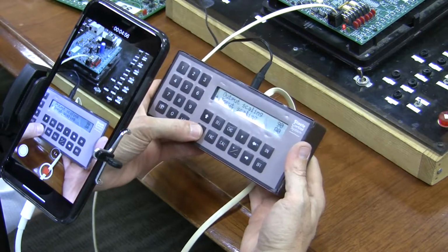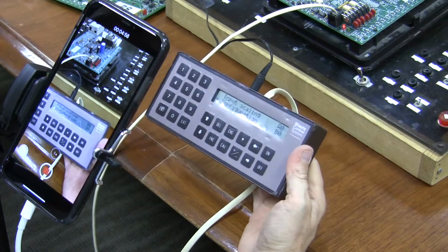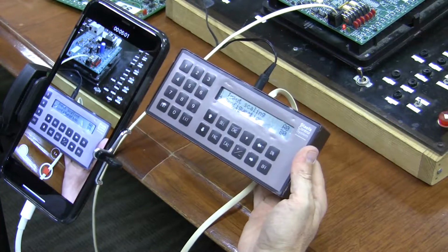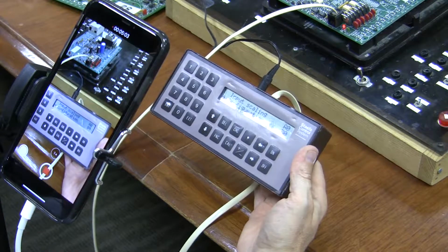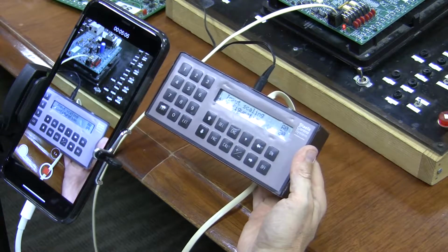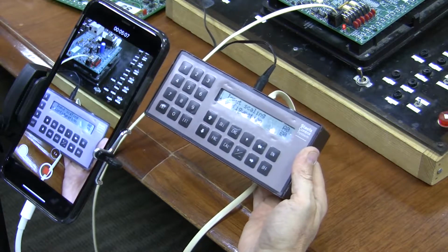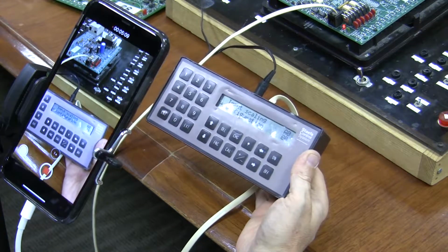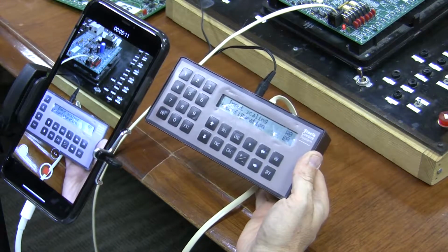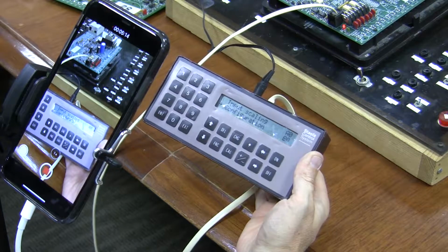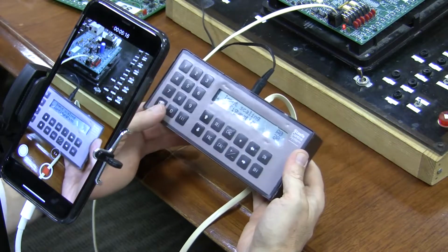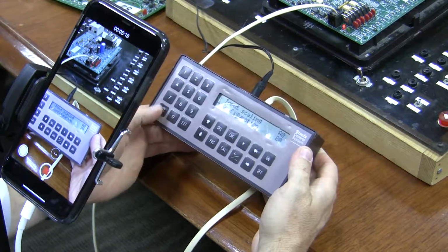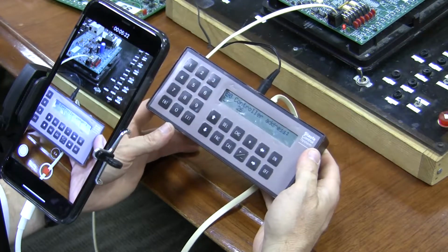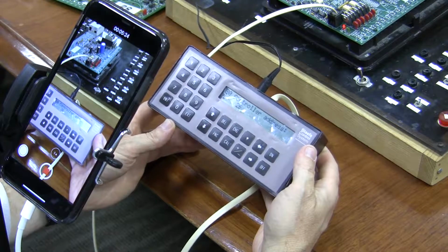And then the same thing, I have an input scaling. Now this configuration is important, because if you ever had to discuss things with the control shop and say I have a problem with a certain controller, they may want to know what address that controller is. So if I came to the 10s and hit enter on configuration, the first parameter, B0, is the controller address. In this particular case, the address of this controller is 26.